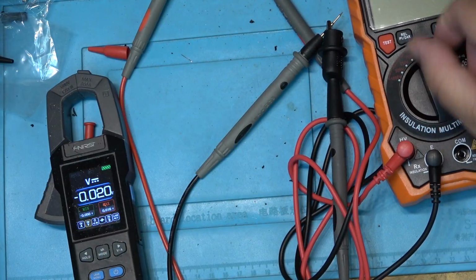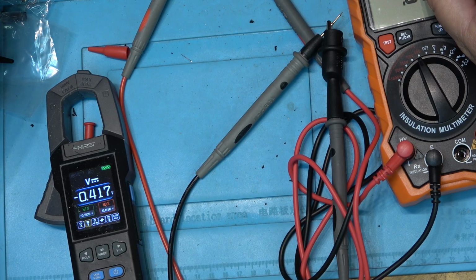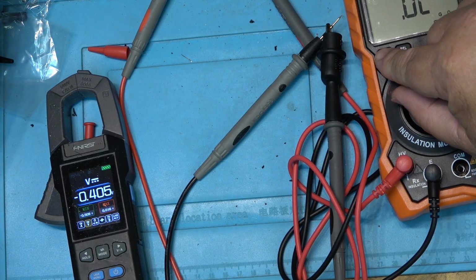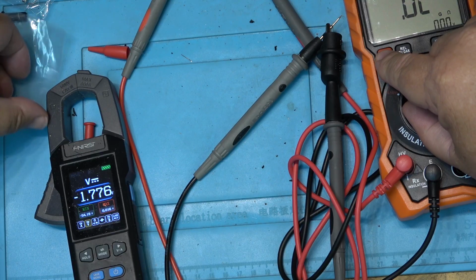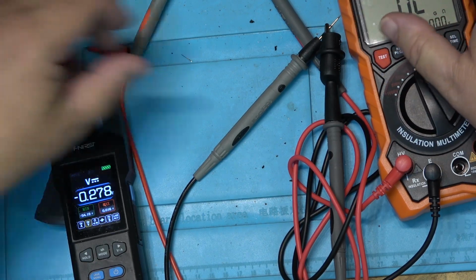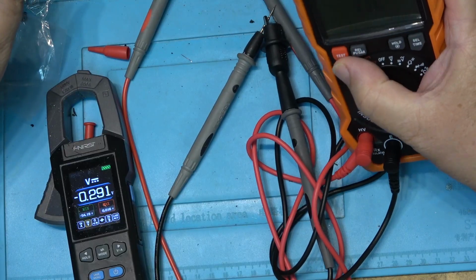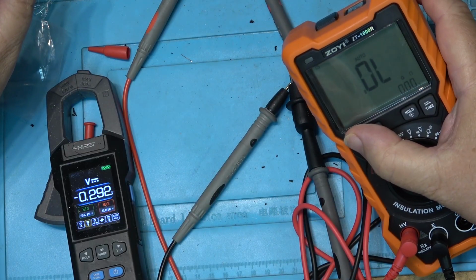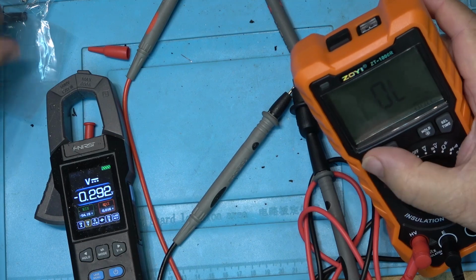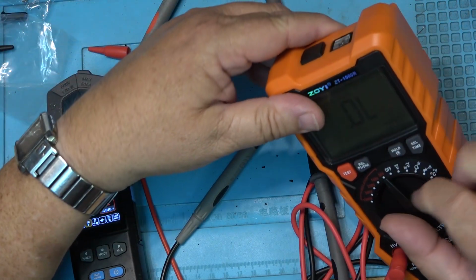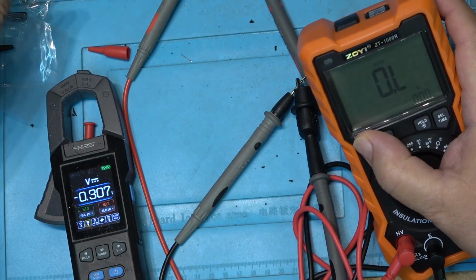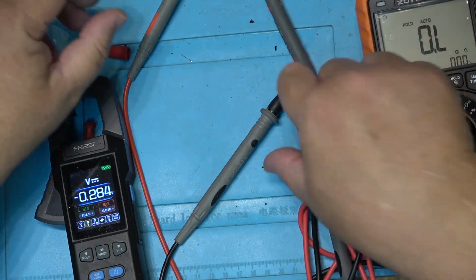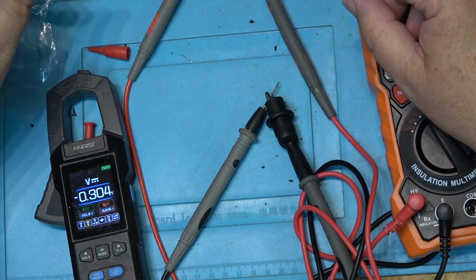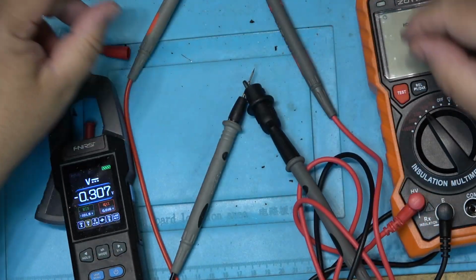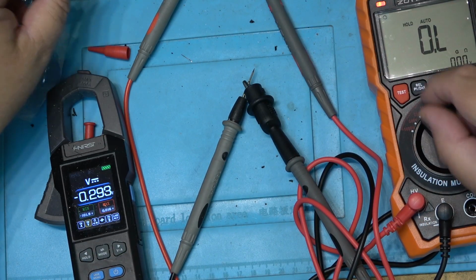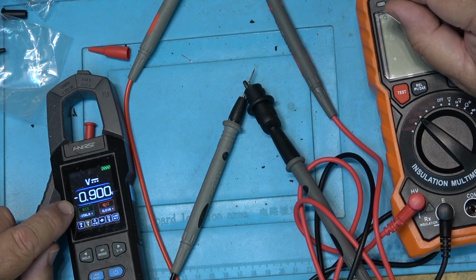Positive and negative terminals. So we'll set it for 50 volts. And I guess I have to hit test. And it does. It puts a voltage out there momentarily, and it'll tell me if there's any resistance breakdown on here. So it does the test. It does do the 50 volts. You'll see, if I go to 100 volts, it's going to send 100 volts down. The polarity seems to be opposite, saying negative. 250 volts, and indeed it did 250.